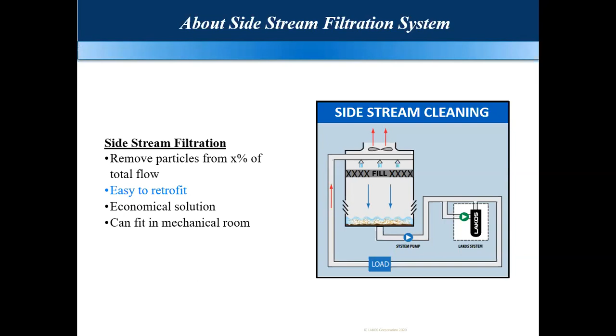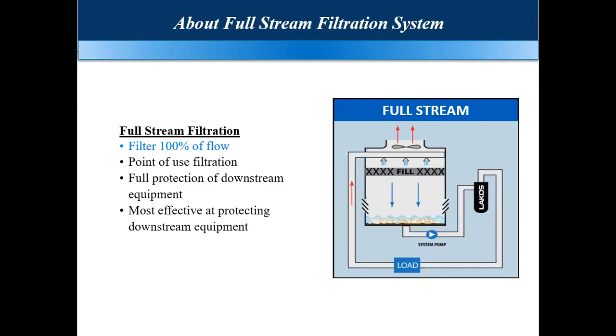The third solution is a full stream solution. It can be applied in small systems, basically, right? Full stream, as the name suggests, for a 100 TR cooling tower, you will have a 300 USGPM type flow rate, so you can have a 300 USGPM separator itself. It doesn't require an additional pump. The condenser pump pushes through that separator. All the dirt is absorbed by the separator, and the clean water goes to your condenser. That's actually the most effective, because you are keeping your parent equipment, the condenser, fully clean, right?